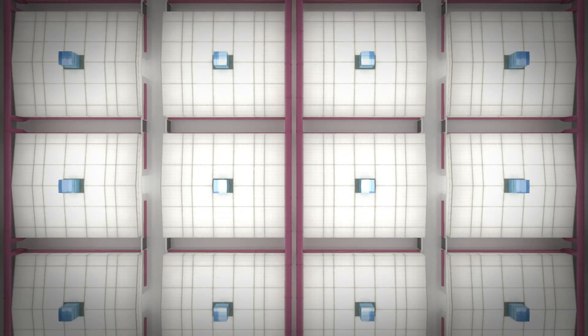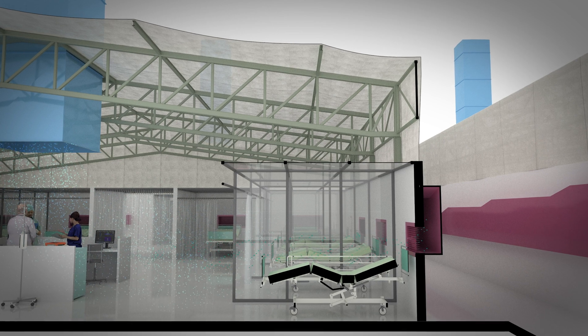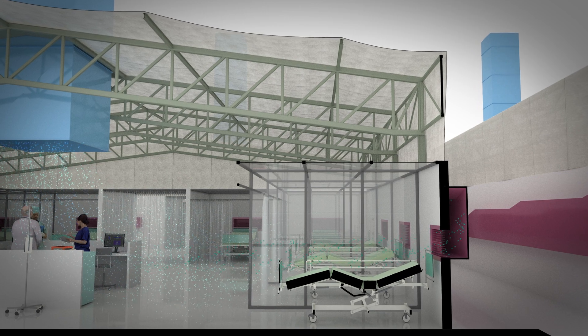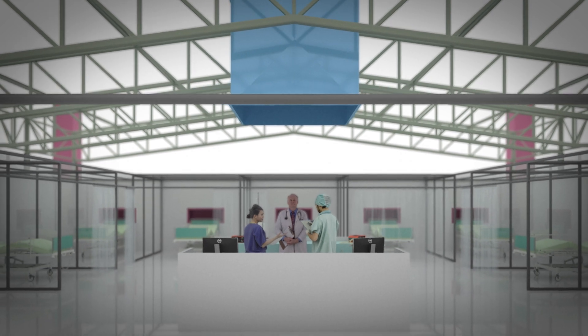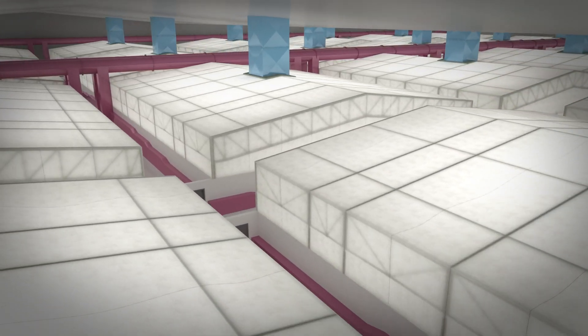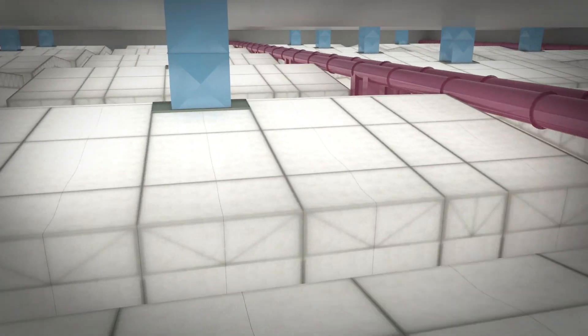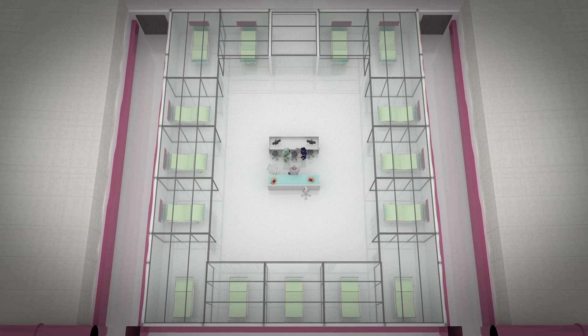In this scheme, air is mechanically exhausted around the perimeter at bed head height, and has a potentially passive downdraft supply of evaporatively cooled air droplets into each ward from a wind catcher at roof level, through a cool tube of micronized sprays. As the mist evaporates it cools the air dramatically — down by 14 degrees Celsius. It works very well in hot and dry atmospheres, such as the laboratories of Torrent Pharmaceuticals in Ahmedabad. There is a concern about water droplets surviving into the occupied zone, so the water and equipment must be kept extremely clean.